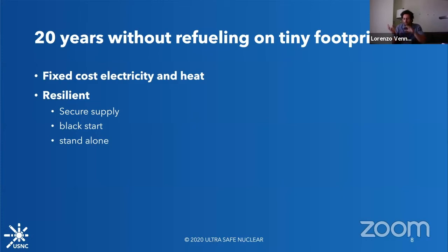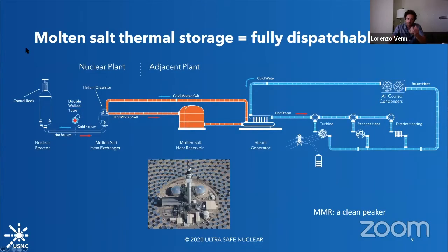It's hard to appreciate, but there's no pipeline coming in, so you don't have to worry about your supply. You've got 20 years worth of energy right there in your one reactor, or multiple if you have a larger site. And of course, it's resilient — you can black start it, it's standalone, you don't need an external grid. The other key feature that makes this really useful is the molten salt thermal storage. That's what gives it the 100% dispatch capability. The way it works is the heat is generated in the reactor, and we control it partly through the control rods, partly through the flow of helium.